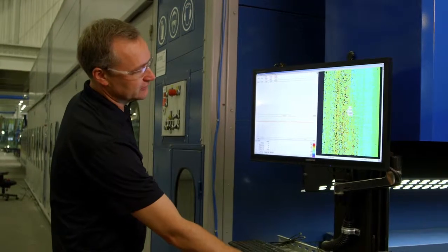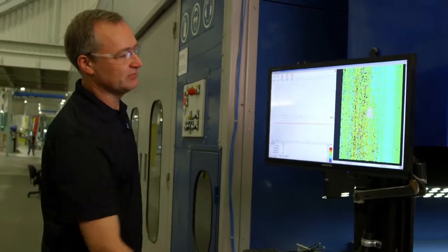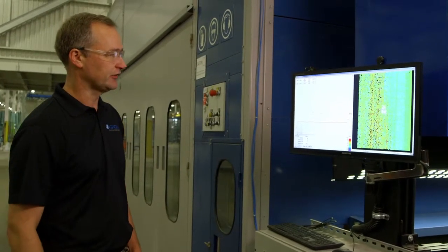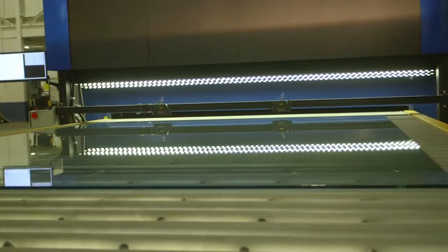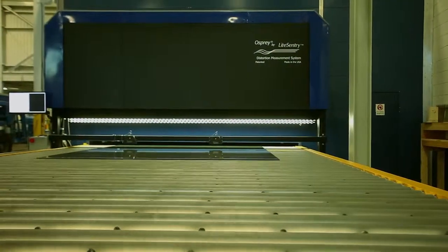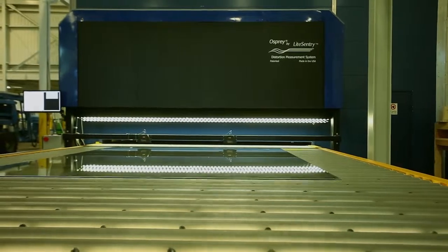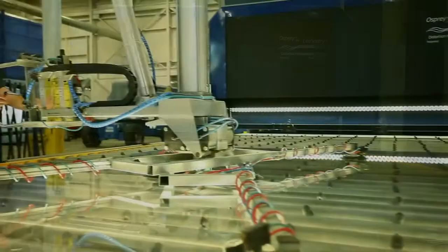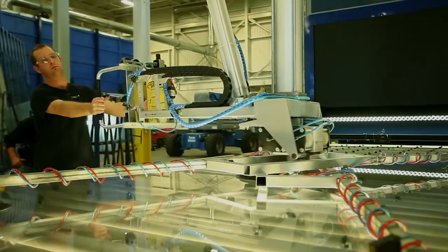And it will vary depending on the actual location in the glass, the front end, the back end, wherever else. The data is based on the radius of curvature of the glass in any given small area. These values can be associated with what the human eye will see when it looks at the actual glass surface. The measurement takes into account all types of distortion in the glass, not just roller wave.